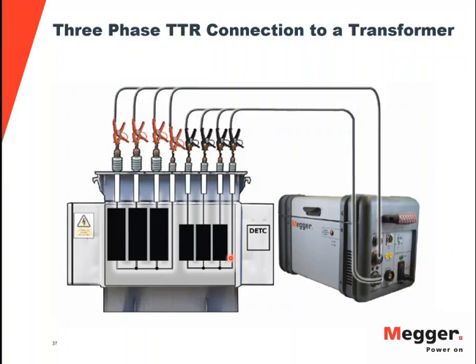In addition to that, you may have a tap changer on those auto transformers, and sometimes I've seen that. I will try to explain it a little bit in depth. So typically your tap changer has plus or minus 10% voltage regulation. And if you think about 33 tap positions, that would give you 5/8% of voltage regulation for each tap transition.